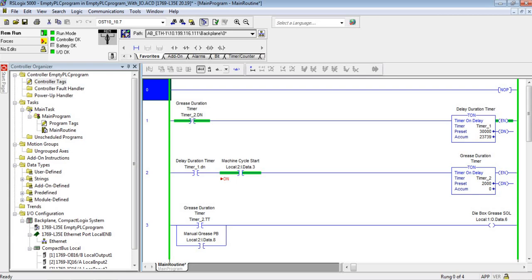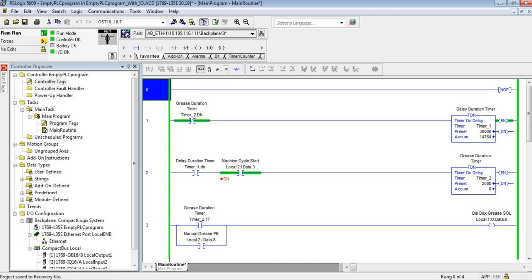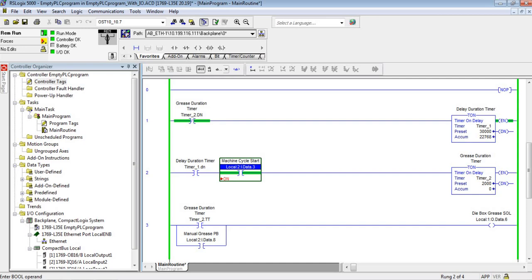I want to show you real quick - I'm using two timers. You see timer one right here and timer two right here. In this example, timer one is set for 30 seconds, timer two set for two seconds. One is called the delay duration timer, the other one is called the grease duration timer. I have a force on this input because I'm sitting at my desk in a lab and I don't have any real-world input, so I'm simulating a machine cycle start condition.